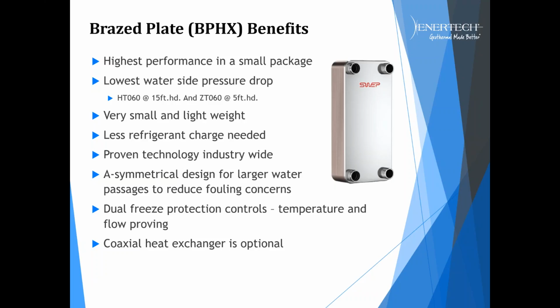Enertech also upgraded their controls, primarily to make sure that we, again, do not freeze this heat exchanger. So what we've done is we've gone to not only freeze protection temperature sensing, but we've also added in flow proving. And the flow proving isn't just a flow switch or a paddle switch that's the same switch for every machine. The flow switch is actually sized based on the tonnage of the unit. So a 2-ton unit would have a smaller flow switch than a 5-ton because your minimum flow for each changes, but we've set that flow switch for the absolute minimum we could see for each specific size unit. So it's very detailed, highly engineered, not just a standard paddle switch that works for everything. And again, we do have the coaxial heat exchanger optional, which will come out here in 2017.